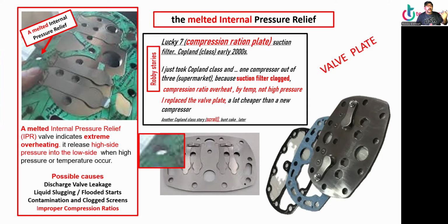That was my problem. So, supermarket customer, Robby story. Also, because I just took the class and the scope of the class, the suction filter was clogged. My compression ratio was bad. Instead of changing a $7,000 compressor for $900, I think I replaced the head, all done with. Those prices are cheap. That was a long time ago, back in the early 2000s.